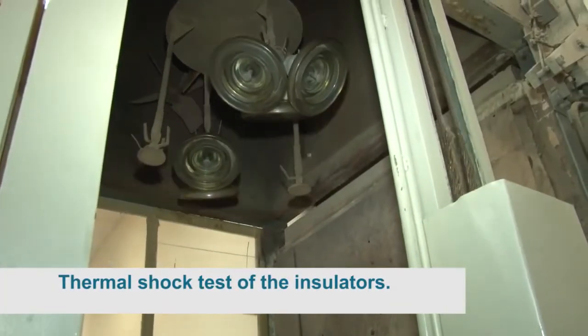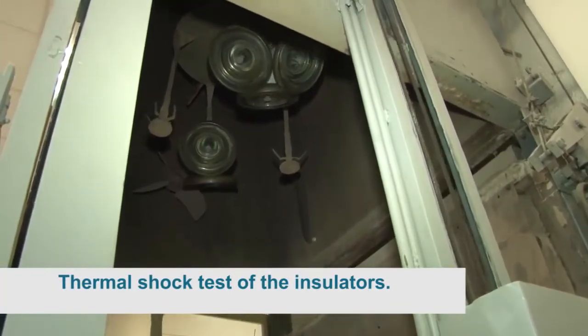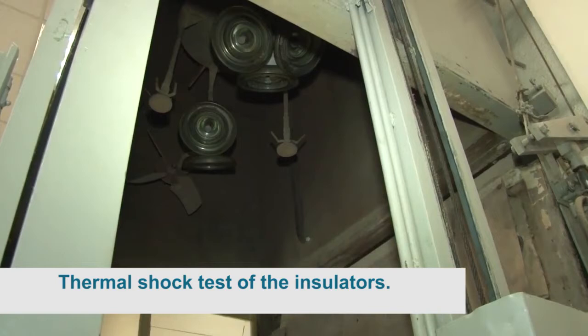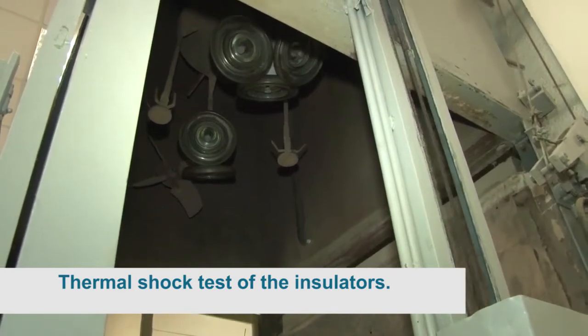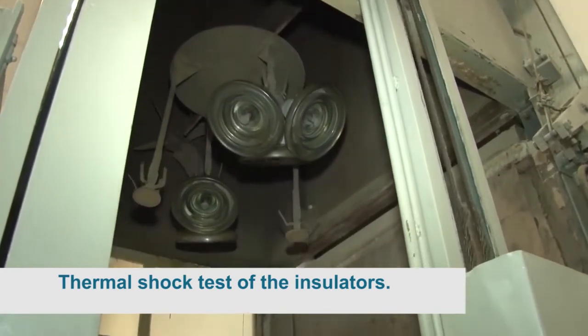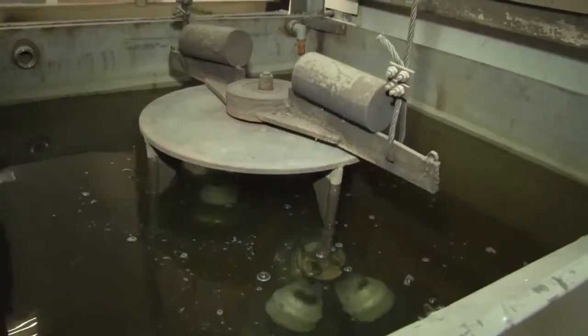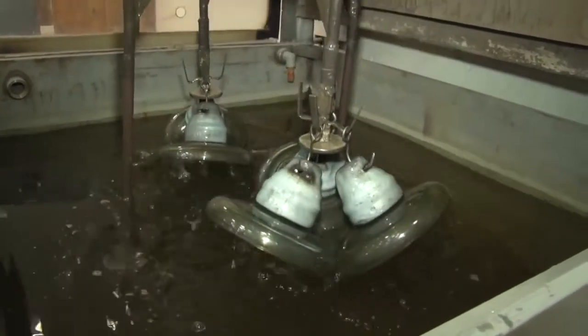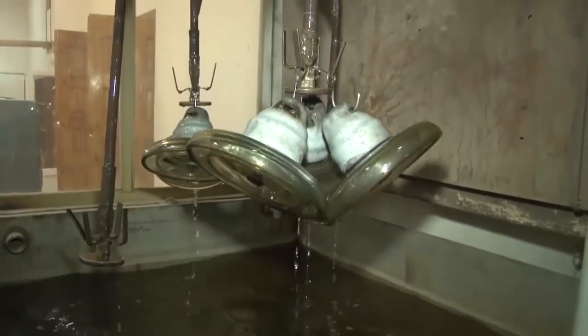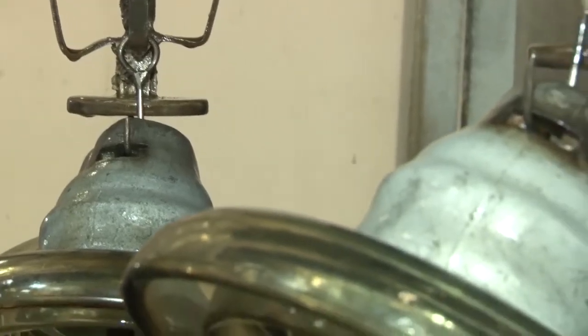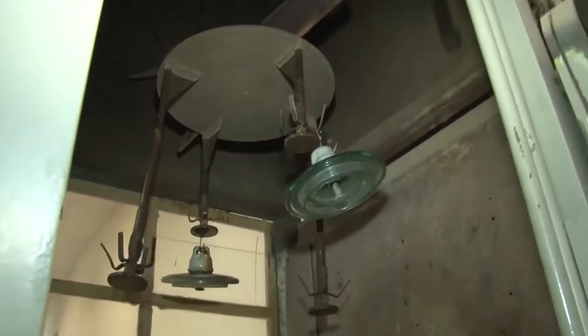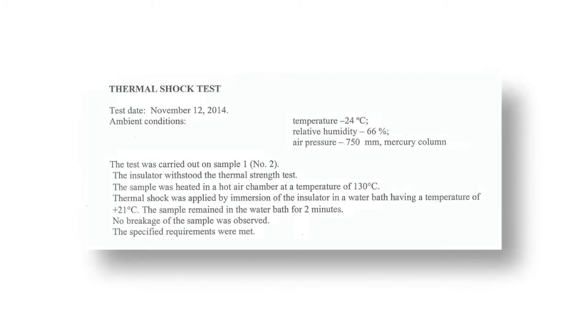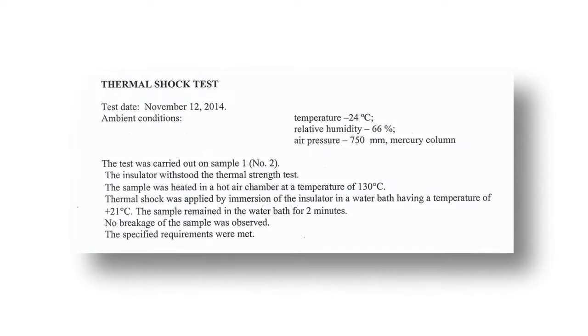Thermal shock test of the insulators of type PS12A and PS70E. During the test, insulators were placed in a heating oven to 130 degrees Celsius above zero. The insulators remained at this temperature for the next 3 hours. After that, the insulators were completely submerged into a bath of water, which is 21 degrees above zero, and remained submerged no less than 2 minutes. As a result of the test, during the visual inspection, no cracks or fractures in the cement joint of the insulators were revealed.